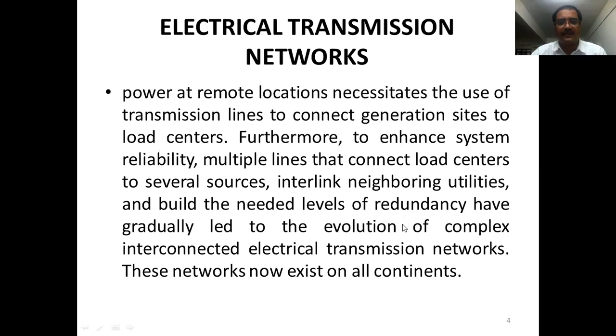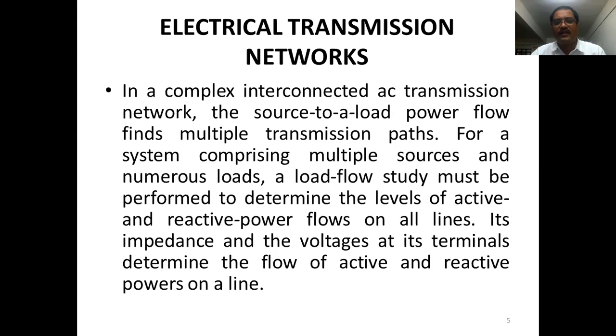In a complex interconnected AC transmission network, the source to load power flow finds multiple transmission paths. For a system comprising multiple sources and numerous loads, a load flow study must be performed to determine the level of active and reactive power flows on the lines. Line impedance and the voltages at its terminals determine the flow of active and reactive powers on the lines. The result is that whereas the interconnected AC transmission network provides reliability of power supply, no control exists on the line loading except to modify it by changing line impedance by adding series and or shunt circuit elements, capacitors and reactors.